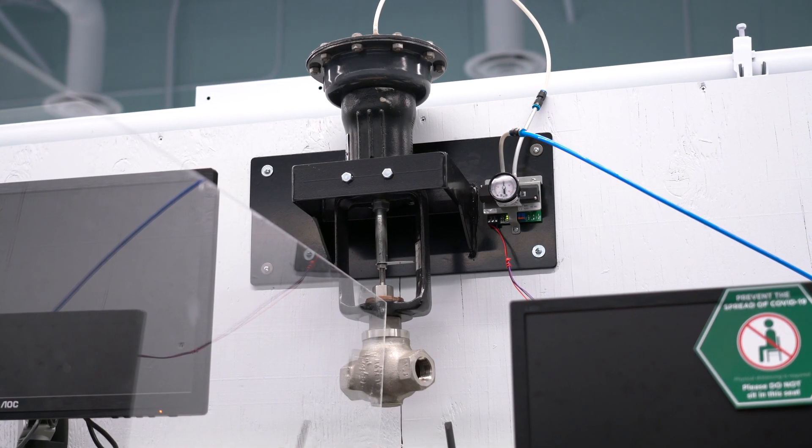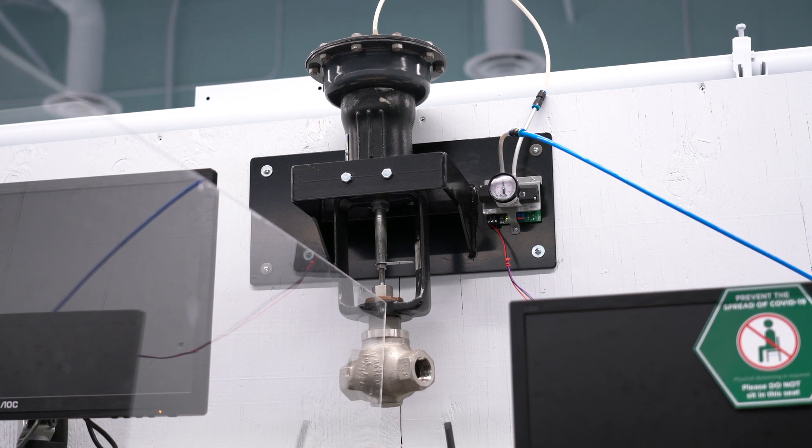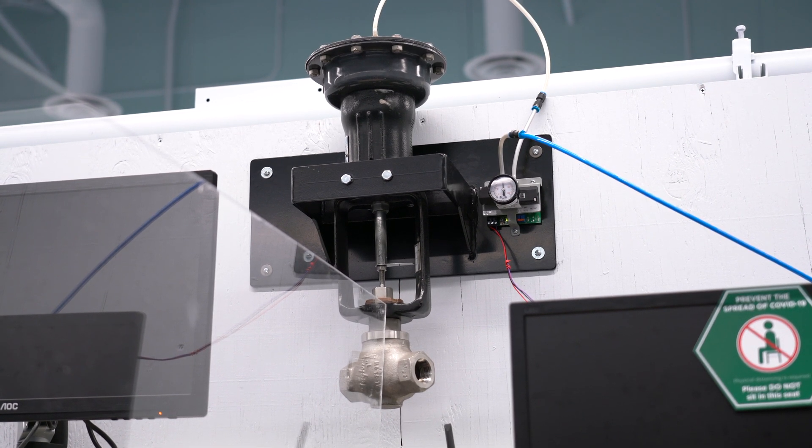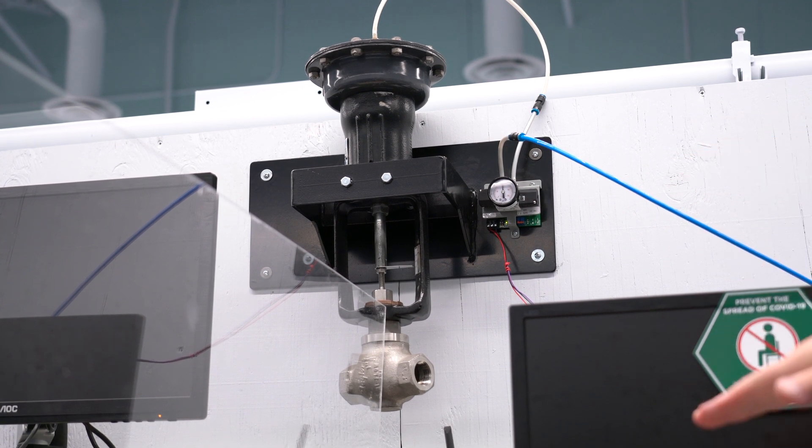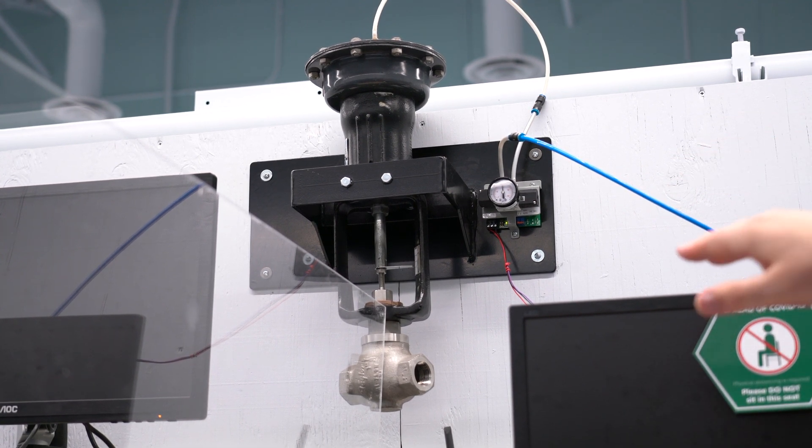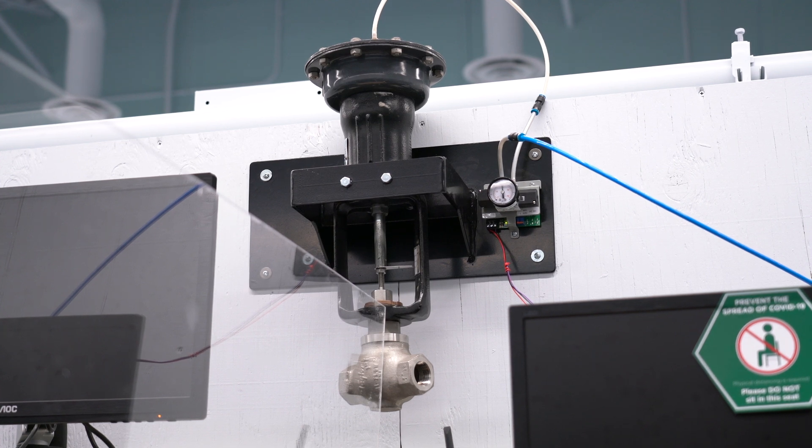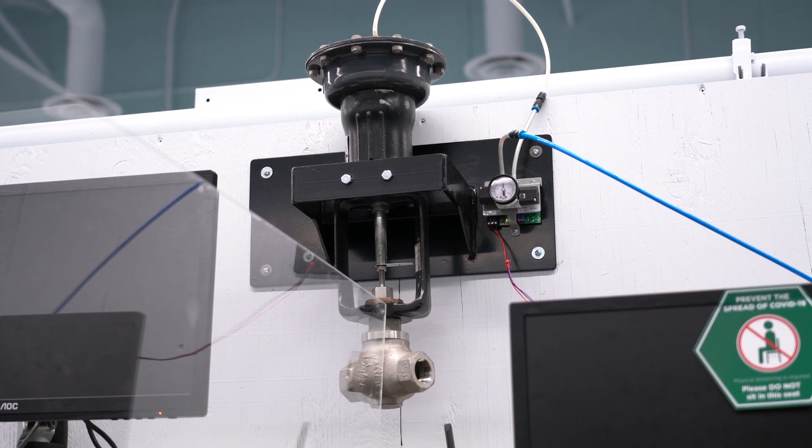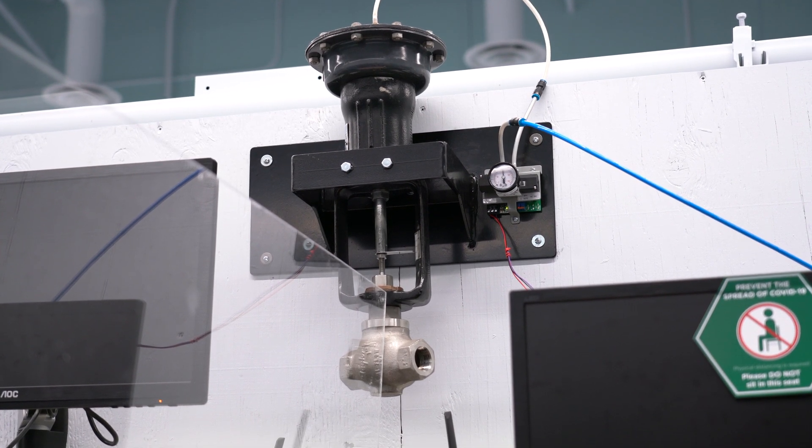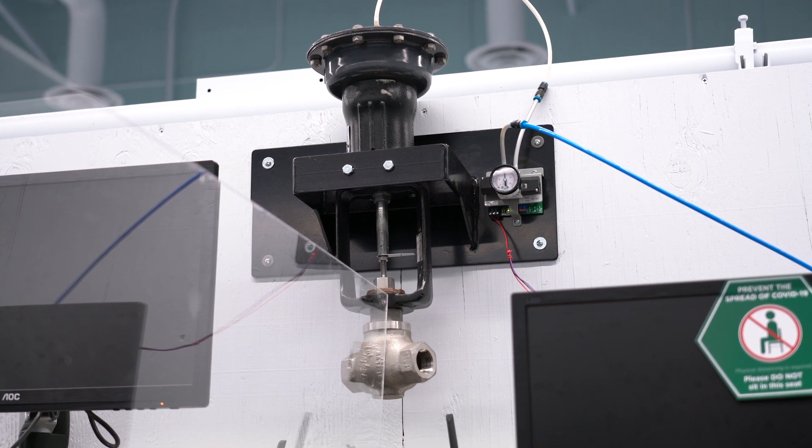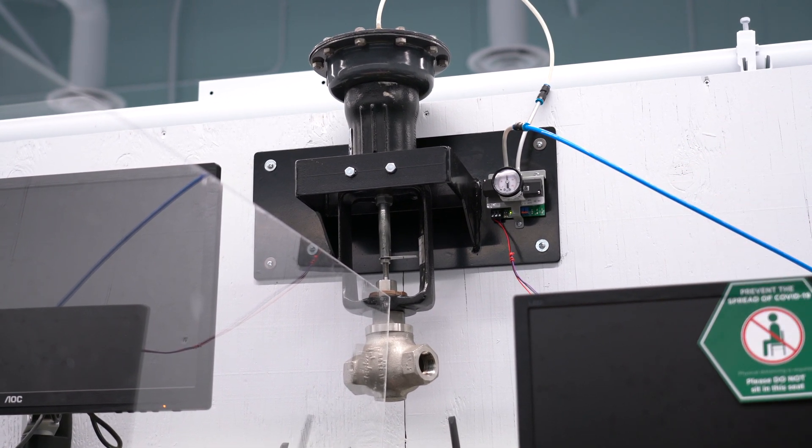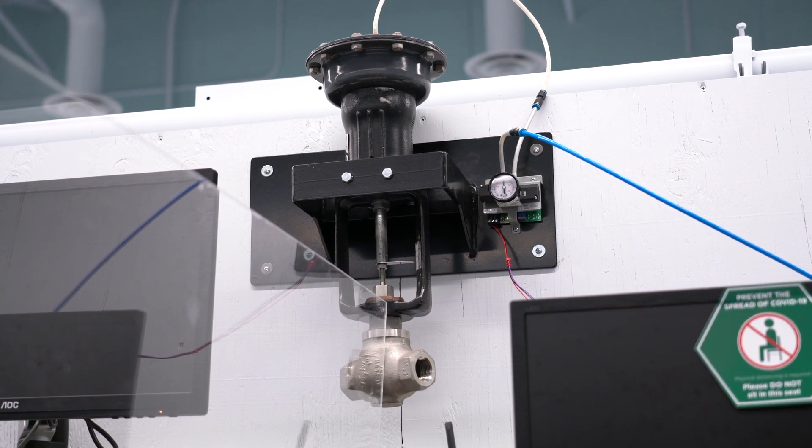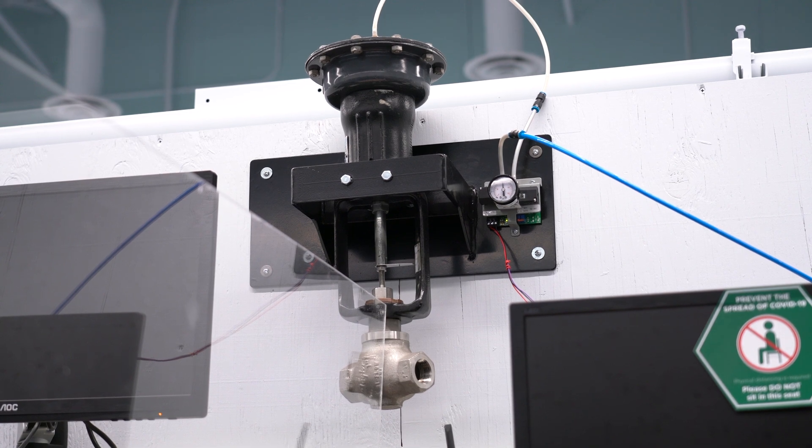Okay, what we have here is a pneumatically controlled valve. At the top is a diaphragm, and air coming into that valve pushes down on a piston rod to open and close the valve down at the bottom. That valve might be used to control the flow of water, so on one side you have water pressure coming in, on the other side the water comes out of that valve, and we can control the water flow through that stem. The air comes in, pushes down the stem, and opens and closes that valve. But it's a linear control valve, so it can be 25% open, 75%, 50%, whatever you might want to have.